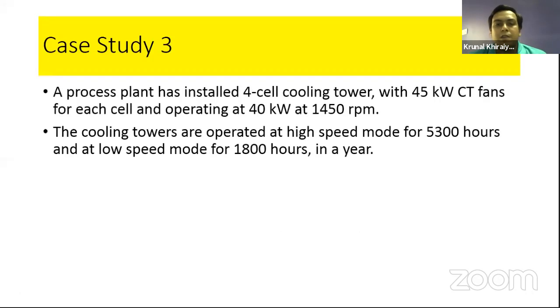Now we discuss case study 3. This is a very important case study because here we are applying an approach of energy conservation and we have good results. In case study 3, a process plant is installed with a 4-cell cooling tower with cooling tower fans of 45 kilowatt. Each cell is operating at 40 kilowatt and at an RPM of 1450. The cooling tower operated at high speed for 5300 hours, and at low speed it operated for 1800 hours in a year.